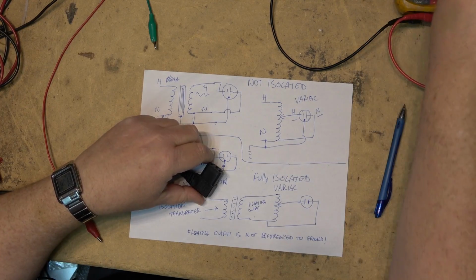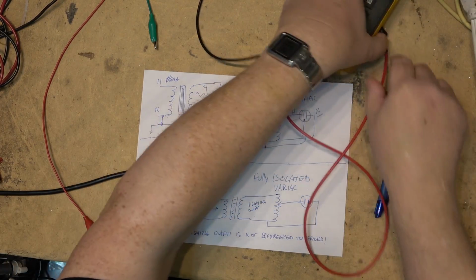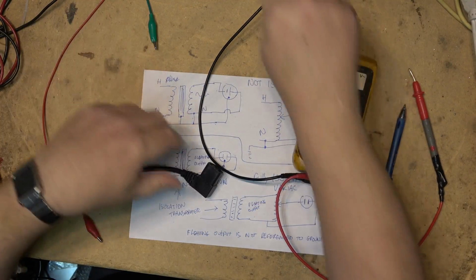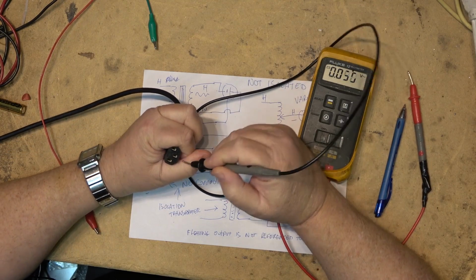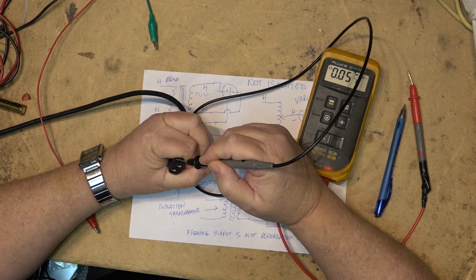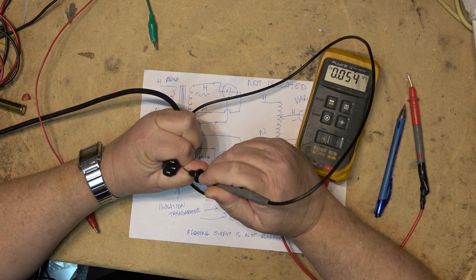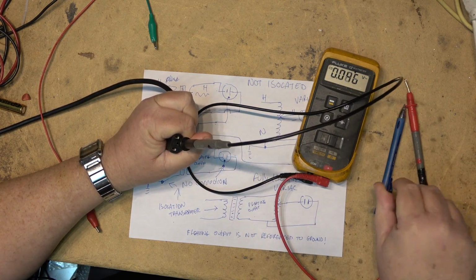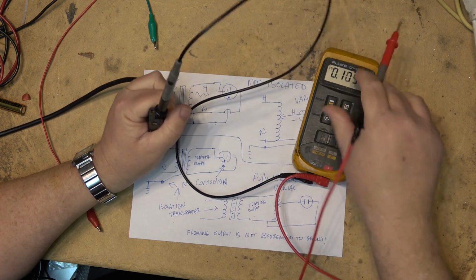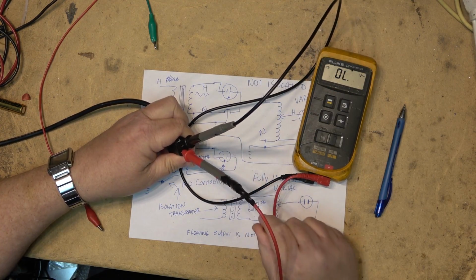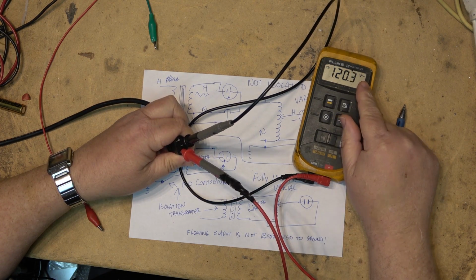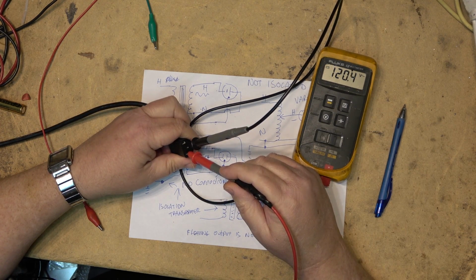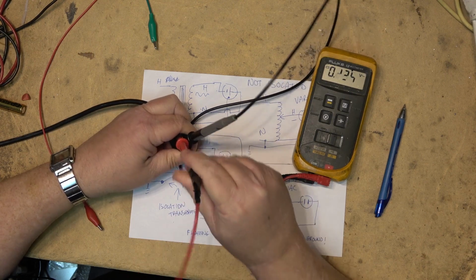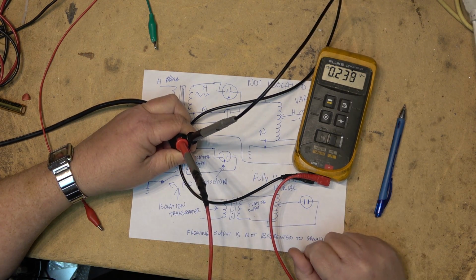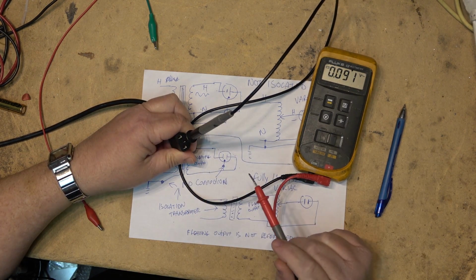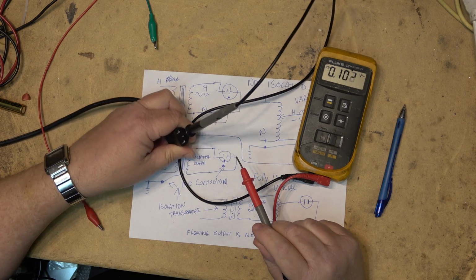If I take my meter and I put the ground, so this is going to be line, ground, neutral. If I put my negative probe or black probe, because I want AC, and I measure here, we have 120 volts between line and ground. And between neutral and ground, we got 0.2, which is probably what the meter is going to measure anyway, just from picking up crap in the air.